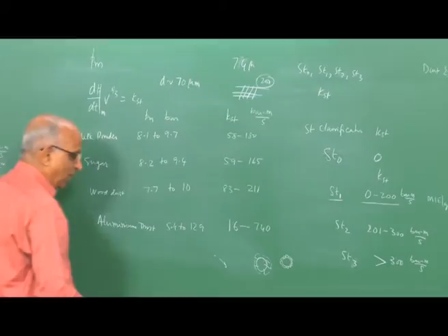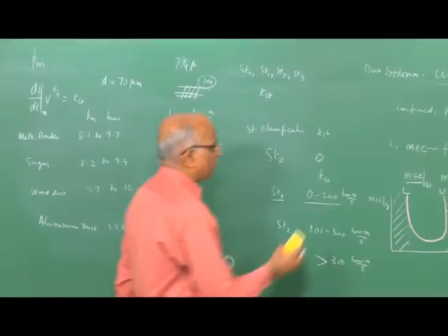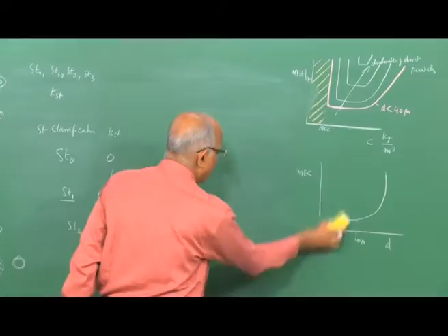Having said that, let's go still further and see whether we can put a number on the severity of the explosion. Having talked of Pm and also (dP/dt)m, that means the maximum pressure and the maximum rate of pressure rise, when a dust explosion takes place you have the maximum pressure and the maximum value of dP/dt, and therefore I can now define the explosion severity. The consequences of an explosion depend on the severity, and it is more severe when Pm is high, that is the maximum pressure is high, and when the value of (dP/dt)max is high. Therefore, the explosion severity will be proportional to the maximum pressure and also the value of (dP/dt)m. That means the explosion severity is the product of Pm into (dP/dt)max.